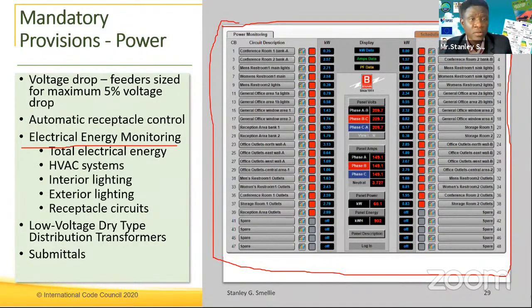You label this and say, okay, this is for the computer lab, this is for the pumps, this is for task lights, and you can schedule what time they come on and off. You can also monitor how energy is utilized through these receptacles over the life of the system. You can also connect specifically your circuit breakers, not just a 110 or 220 volt outlet, but an actual circuit breaker that you monitor, serving your exterior lights, your interior lights for the computer lab, or your interior lights for the corridor.